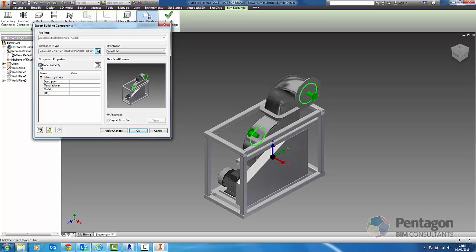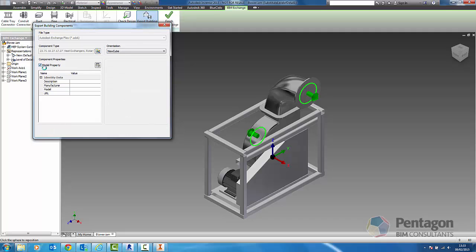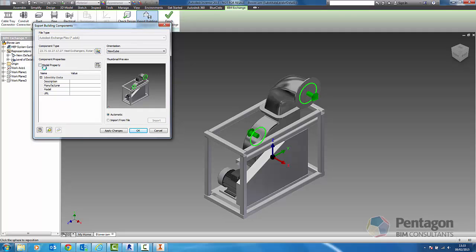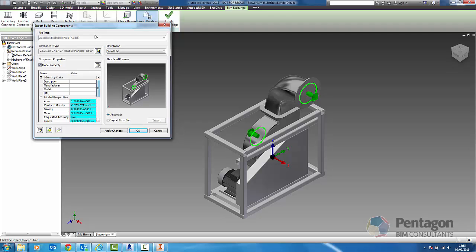We can add in the model property information. You can see in here the center of gravity. That might be very important. This object could be particularly heavy. We might want to use that information in model aggregation software. We might want to use it for a crane calculation, how a lift or hoist is going to lift it on site. We'll tick on the model property information and we'll see that come across. This saves this out as an ADSK file which can be opened natively in Revit.